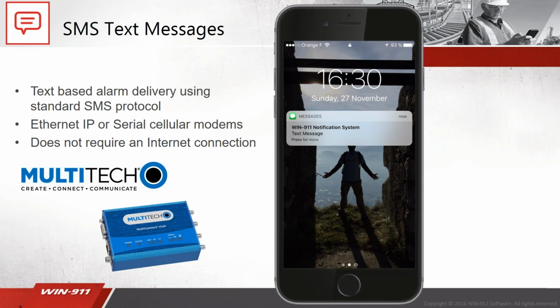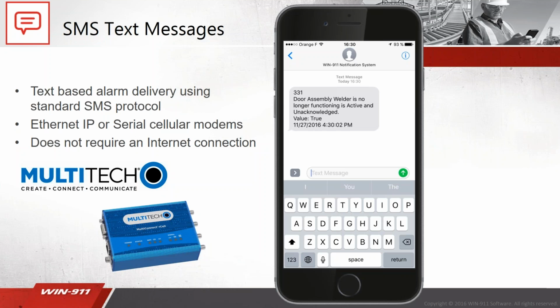We do support those modems too, though, the serial modems, so you can still do that if you want, but these modems are also available. So you can see, just like the push notification, it'll show up on your summary screen there. We'll go ahead and open up the text. You'll see it has a ticket number at the top, just like before. It's a shorter ticket number than before. And if you have more than 199 alarms in your system, that number will grow automatically. So if we want to ack this message, what we can do is we can type in the ticket number and the password that this particular person has, and that password is going to be 123.